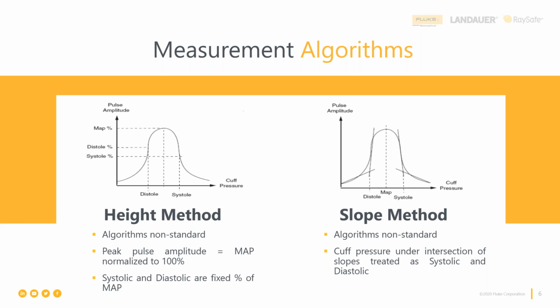The height method is more of a statistical sample approach, but it's usually normalized to 100%, which means it's been manipulated and fudge-factored in order to agree better with comparative auscultatory blood pressure measurements. And that's how they've come up with their formulaic way of managing a more accurate blood pressure reading in the firmware of the medical device. So again, the peak pressure in the cuff is assumed to be the mean arterial pressure, and then there's a statistical calculation of diastolic and systolic pressure values. Okay, so that's the way that it's done. It's more of a statistical sample method.